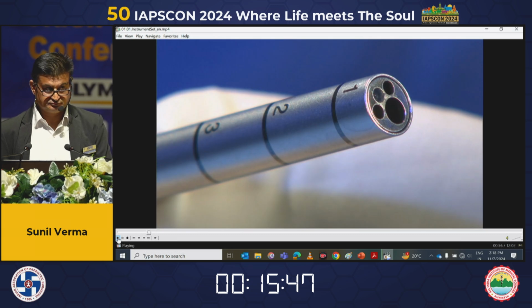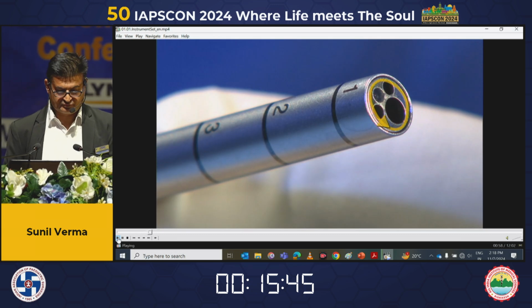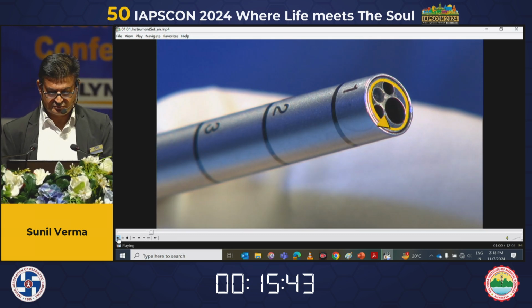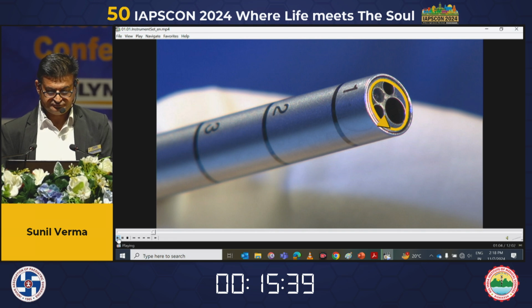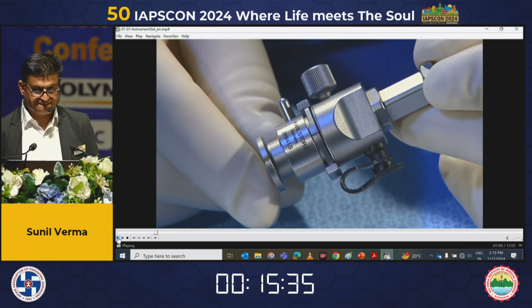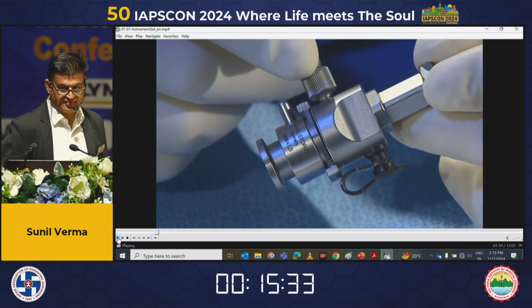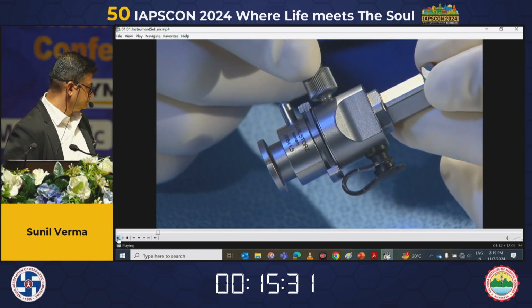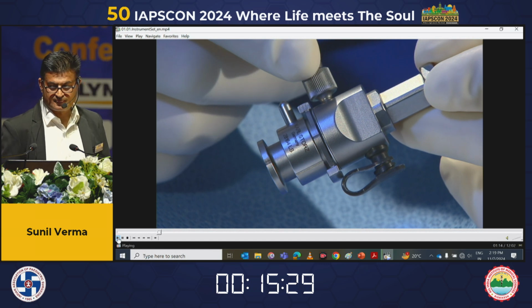Thanks to a rotation mechanism integrated in the endoscope sheath, the endoscope can be rotated without having to release it at the endoscope holding arm. To allow rotation, the knurled screw on the head of the endoscope sheath is simply released and, following rotation of the endoscope, screwed tight again in order to keep the rotation position steady.